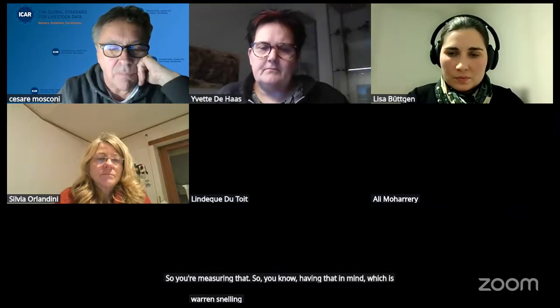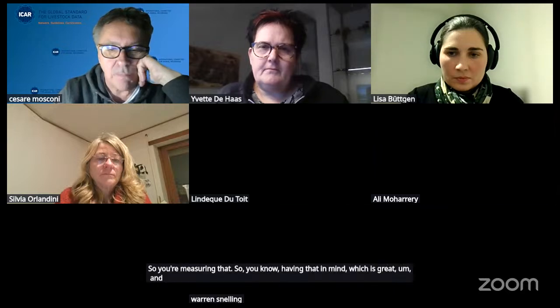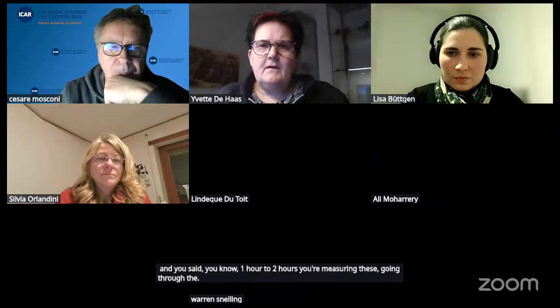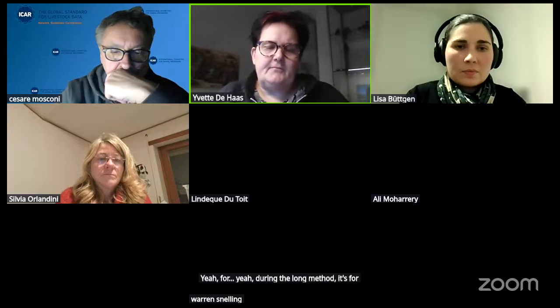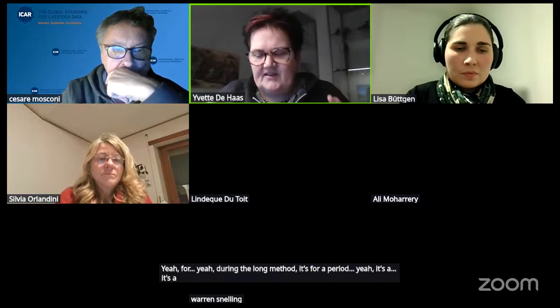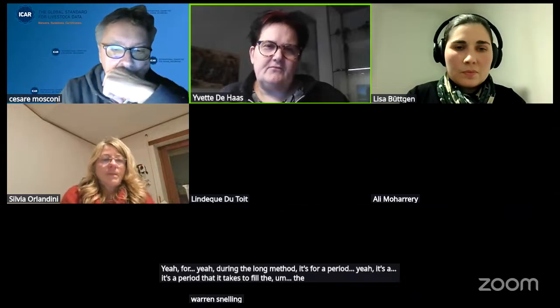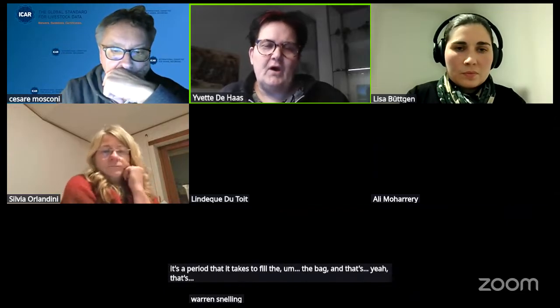Okay, so in other words, it's an average over a period of time, right? Yeah, so you're measuring that. Having that in mind, which is great. And you said 1 hour to 2 hours, you're measuring these going through the device. Yeah, during the long method it's for a period, the period that it takes to fill the bag, and that's close to 2 hours.